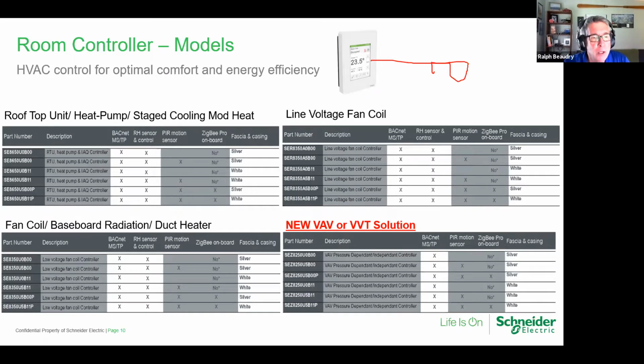But what's really important, and why I got to this point, is that all of these models have a B in them. That means it always has BACnet MSTP on board. There's a free slot on board the 8000 to add different types of plug-in cards. One of them is a CO2 card. The other one is a ZigBee communication card or a Wi-Fi card. Or I can buy it now with ZigBee on board. That's what this P is, if you guys can see that. So that means that there's ZigBee Pro on board, that slot is still free.